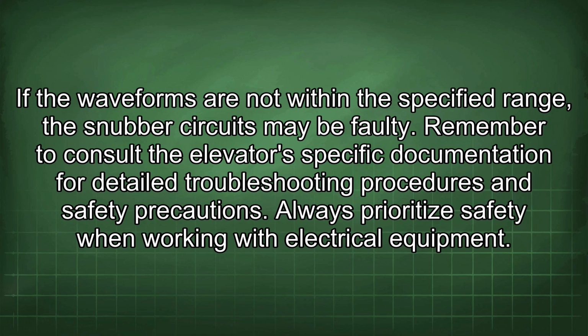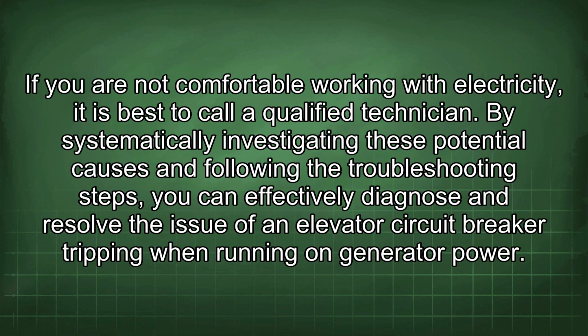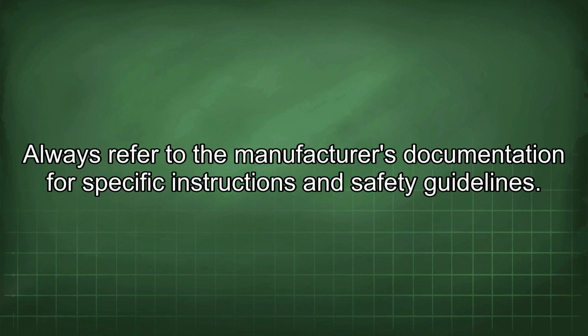Remember to consult the elevator's specific documentation for detailed troubleshooting procedures and safety precautions. Always prioritize safety when working with electrical equipment. If you are not comfortable working with electricity, it is best to call a qualified technician. By systematically investigating these potential causes and following the troubleshooting steps, you can effectively diagnose and resolve the issue of an elevator circuit breaker tripping when running on generator power. Always refer to the manufacturer's documentation for specific instructions and safety guidelines.